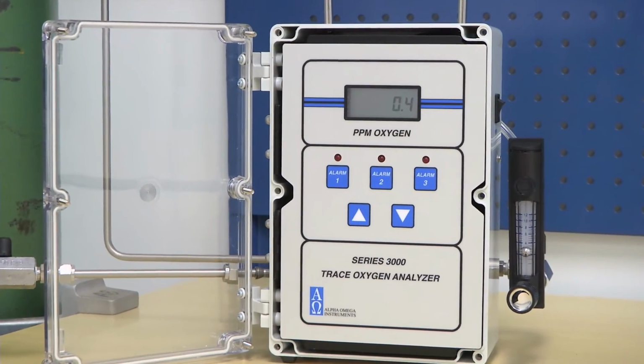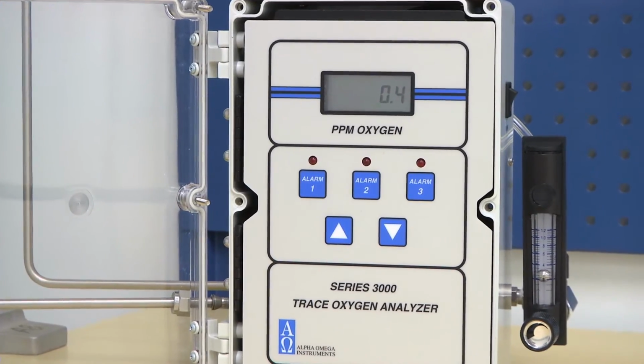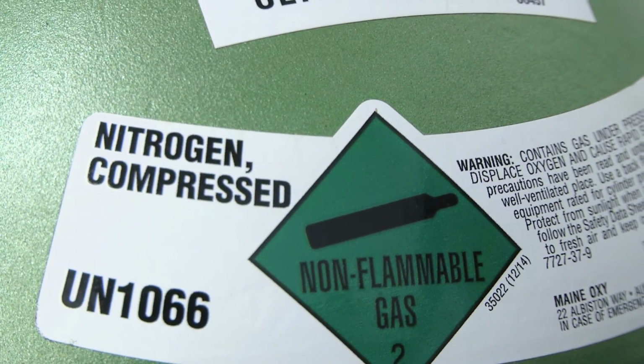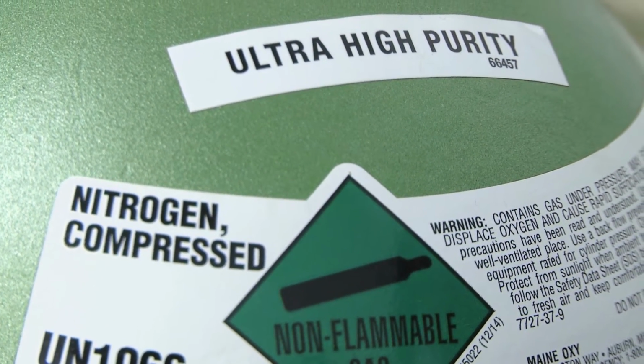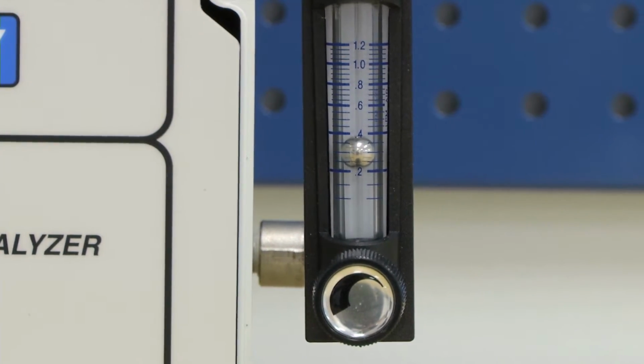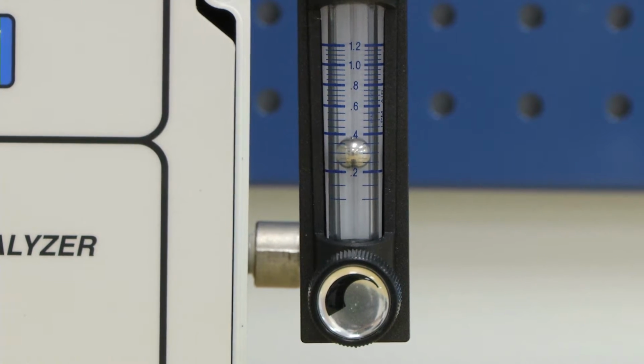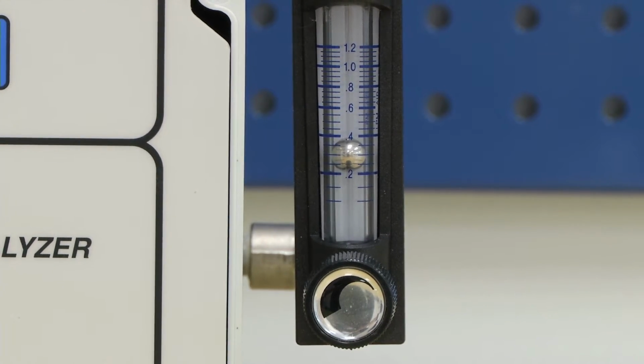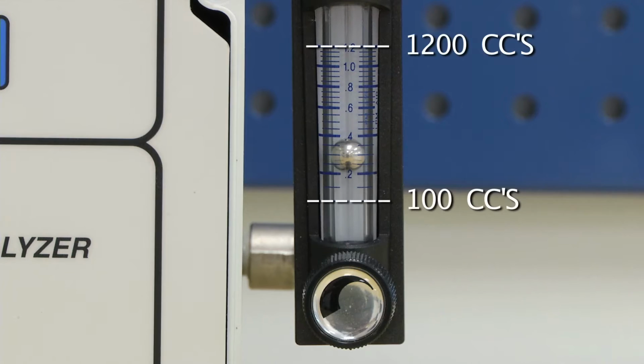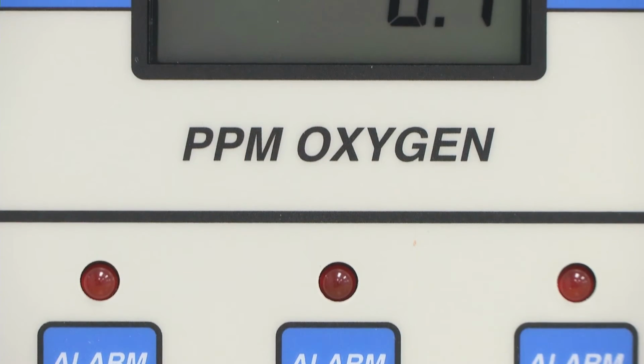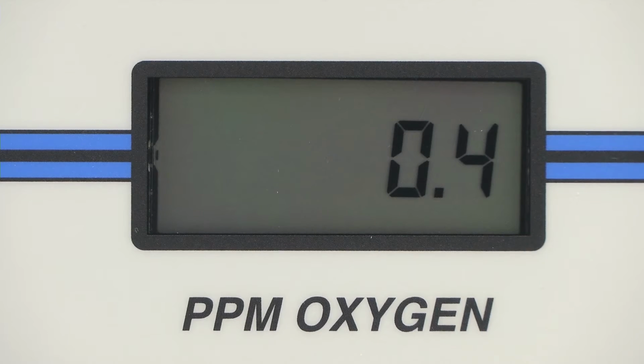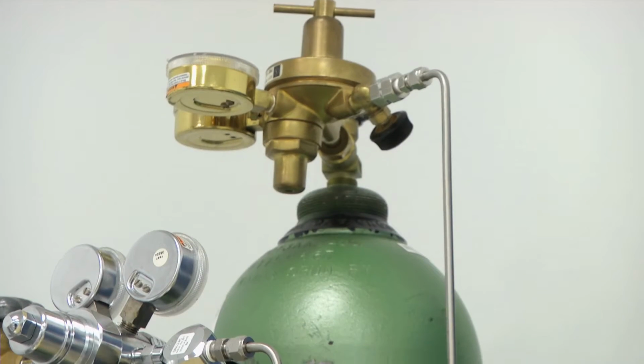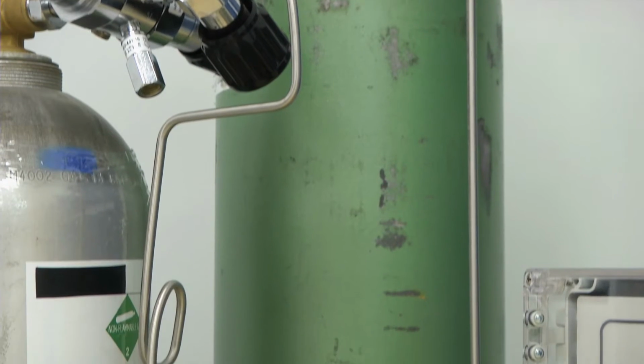At the onset of the calibration procedure, we recommend that the analyzer be powered for approximately 10 minutes. The analyzer shown here is being used to measure ultra-pure grade nitrogen with an oxygen value of less than 1 ppm. The sample flow rate is approximately 300 cc's per minute. By the way, the exact flow rate used when calibrating the Series 3000 is not important, as long as it is between 100 and 1200 cc's per minute. This Series 3000 is reading 0.4 ppm on the ultra-pure nitrogen gas, which validates that this gas delivery system is free of any air leaks.